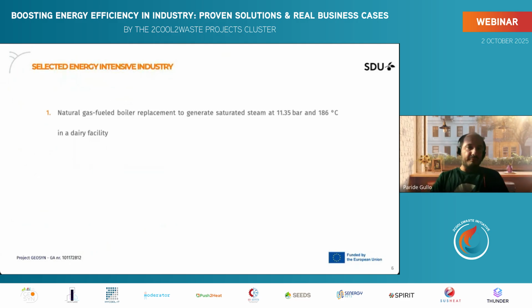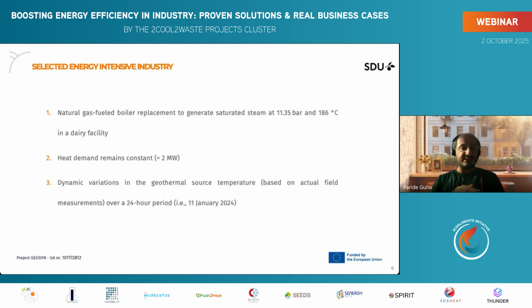Let's look at the selected case study, the selected energy-intensive industry. The results I'm going to show are based on a dairy facility that needs heat at 186 degrees Celsius. Currently they use a boiler with natural gas to satisfy the heating demand, which is roughly equal to 2 megawatts. For our results, we used real field measurements from the actual geothermal well as input to our model, selected a specific day, and used dynamic electricity prices over the 24 hours as well as real values for the price of natural gas.